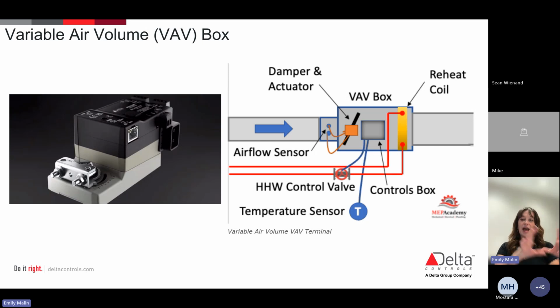We talked very briefly about that control loop and what that looked like. So let's rethink about that. When a thermostat is sensing a change in a room temperature, it's going to send a signal to the actuator, and then the actuator is going to open or close that damper. Usually we see that from about 30 to 100%, which is what will actually adjust that airflow to bring in more or less cool air to the zone as needed. Now, if it's cooler weather and we actually want to heat something up, that reheat coil is going to step in. So our hot water valve will open, the reheat coil will heat, the air is going to flow across that reheat coil, and that's what's going to bring the temperature up in the space. So that's just everything in general when we're looking at a VAV box.